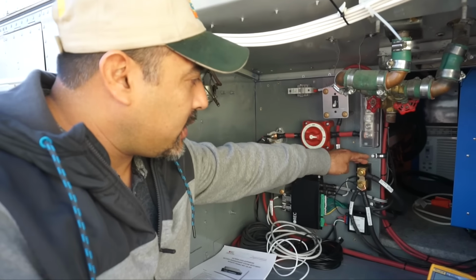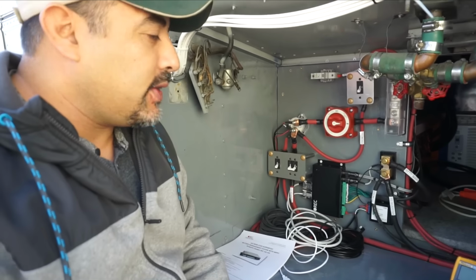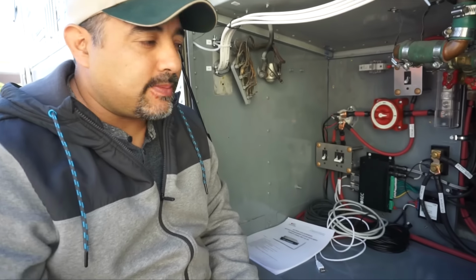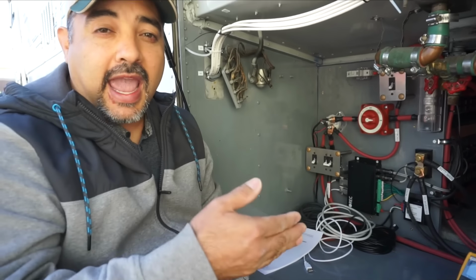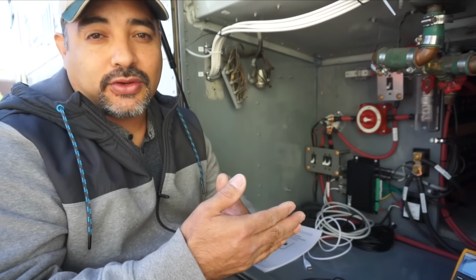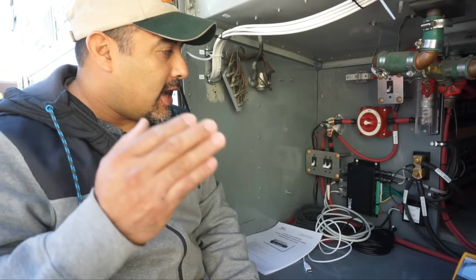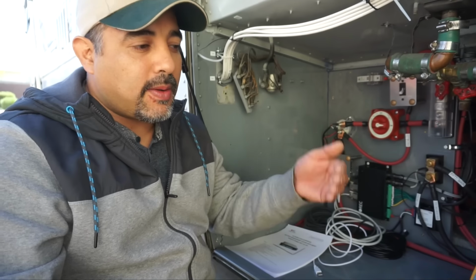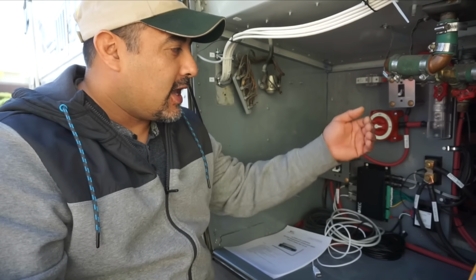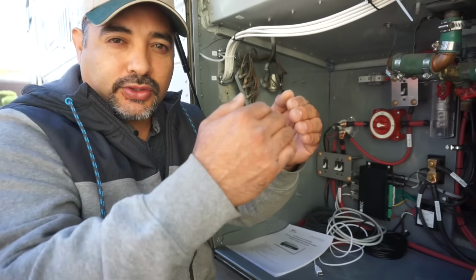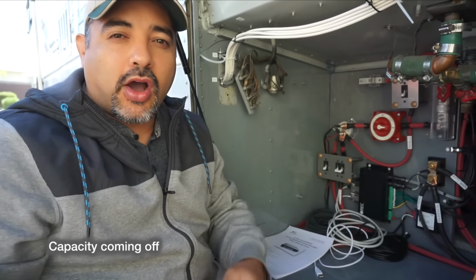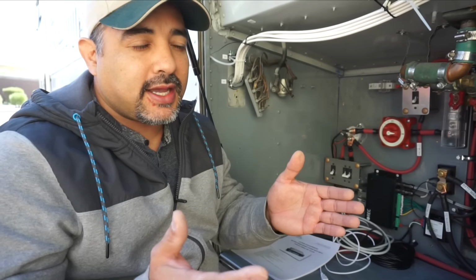If you're not familiar with a shunt, the reason we use one, especially on a lithium system, is it counts the amperage as it goes in either direction. If the battery is getting charged, it shows a positive accumulation. If the battery is getting depleted, it shows amps coming off the battery.